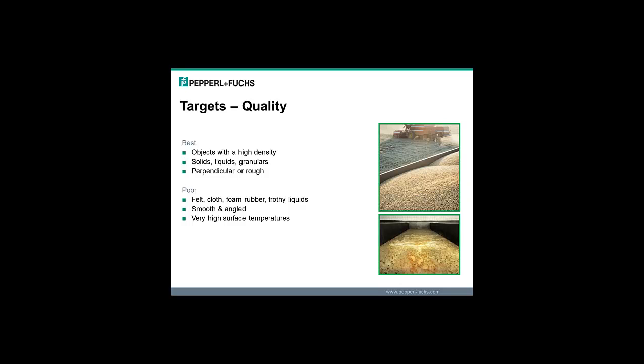And also rougher targets, as odd as that sounds, the rough targets, if you angle them left or right, you can get a lot wider sensing beam angle, and you don't have that issue where you have the sound deflecting off a smooth surface at an angle and not coming back to the sensor. So when that surface is rough, you still have some little corner cubes. It's kind of like bouncing a ball off the ground and into a wall and it comes back to you. When you have the rougher surfaces, you have a lot more of those corner cubes, and it's a lot better target than a very smooth one, like a mirror or a smooth metal plate.